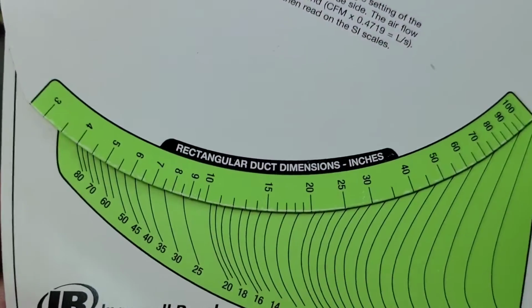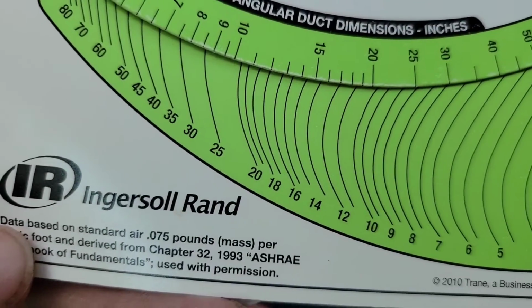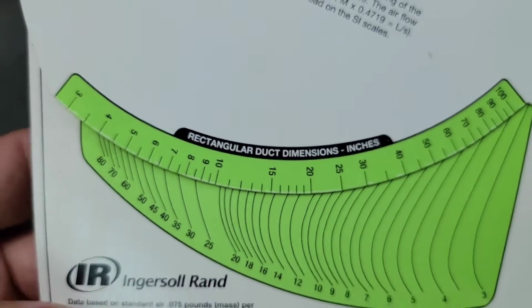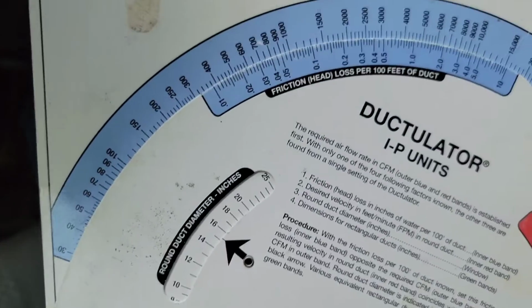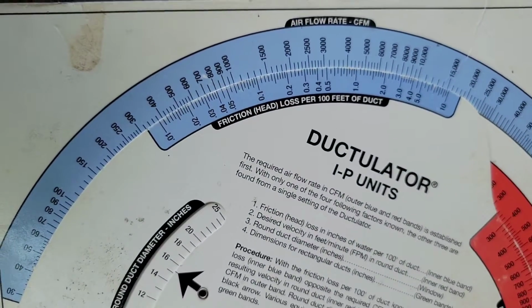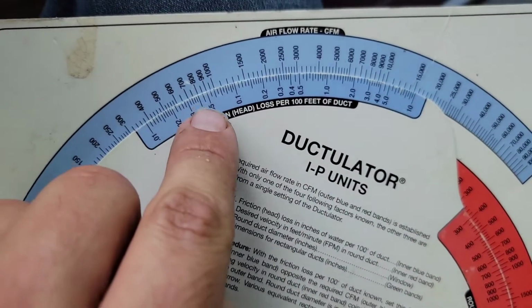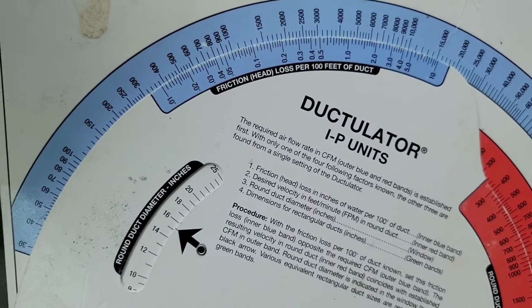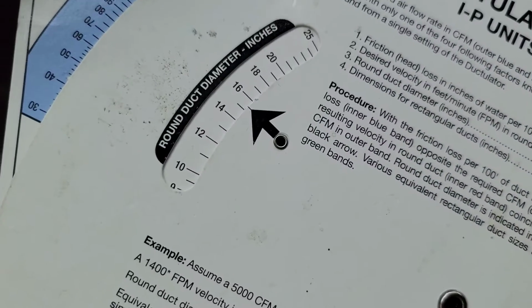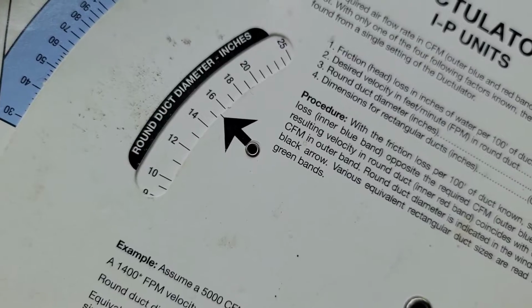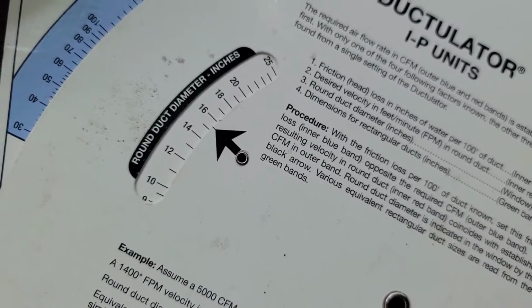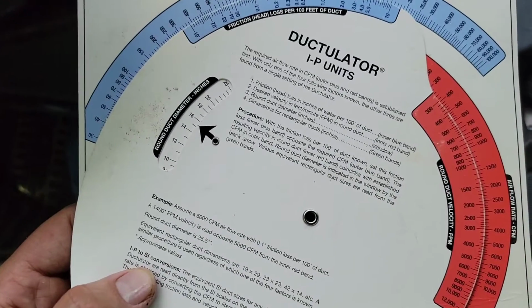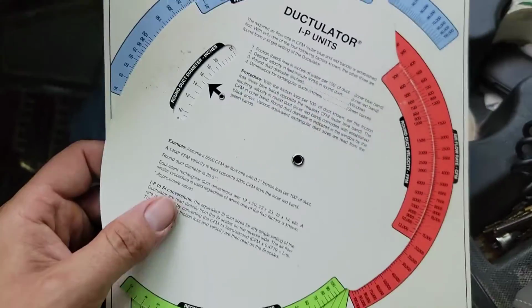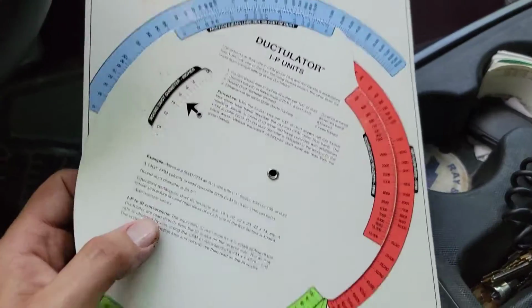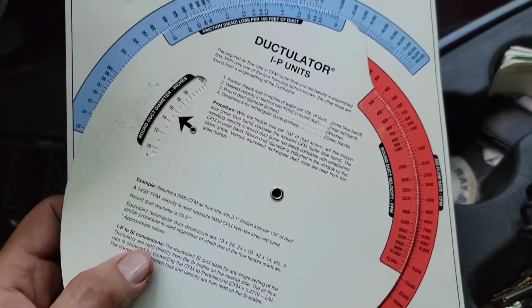So down here I've lined up my 9 with about 24 inches for my rectangular duct dimension. I go up here and it tells me at 0.05 I'm going to carry 900 CFM. That's almost half. And it says about 15-inch ductwork is what we've got. So we need at least 18 on this. We're not able to carry the CFM. This problem has to do with the ductwork, not the unit.